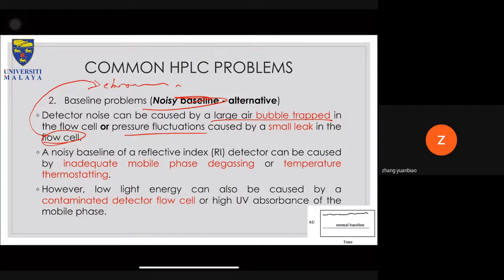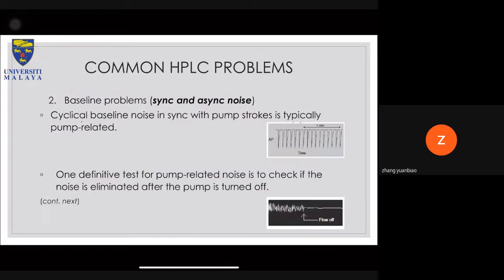All right, synchronous or asynchronous noise. Cyclical baseline noise, synchronous with the pump stroke, is typically pump related. So this one is as what we've touched a little bit. It might be some issue with the pump. Well, there definitely is some issue with the pump normally.